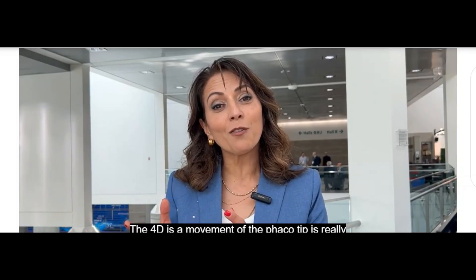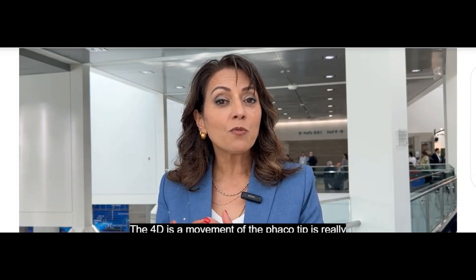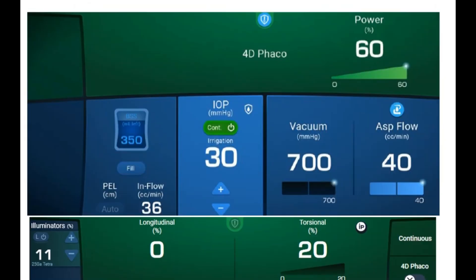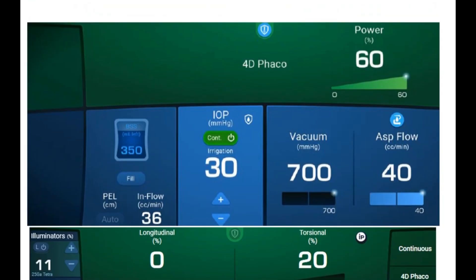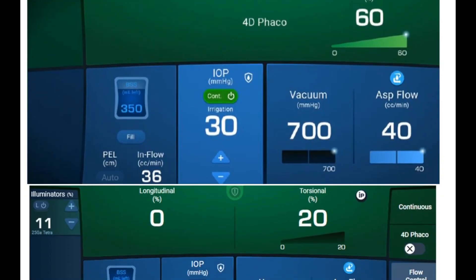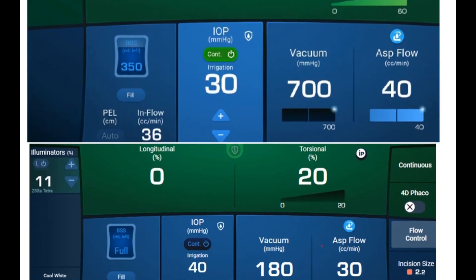4D Phaco refers to the movement of the phaco tip — it's truly multi-dimensional. One might think there's not much improvement possible over the Centurion, but this has increased the efficiency of nuclear fragment removal by more than two times.